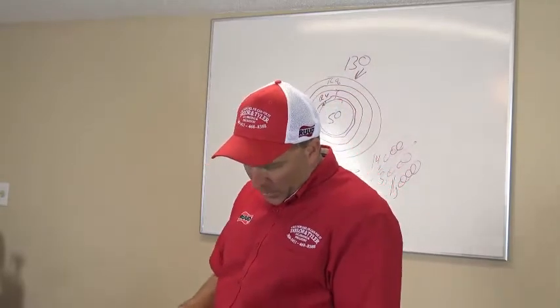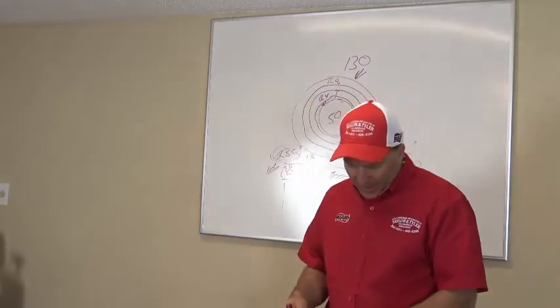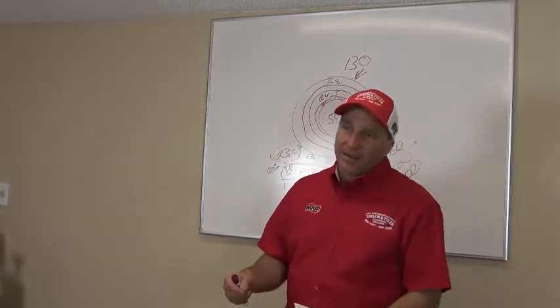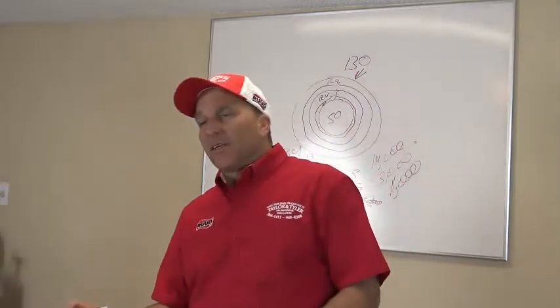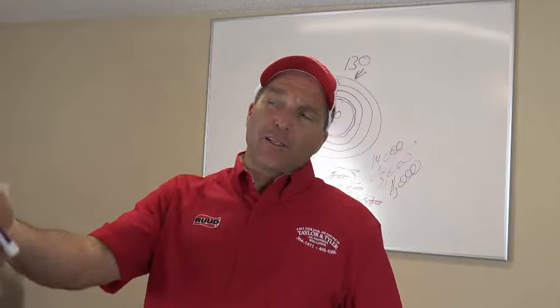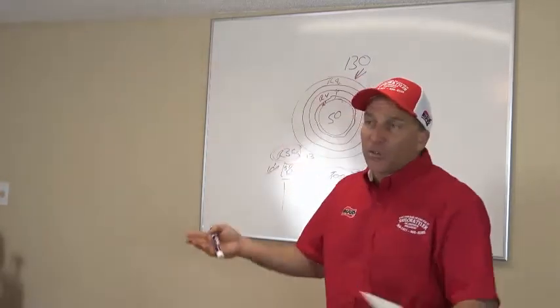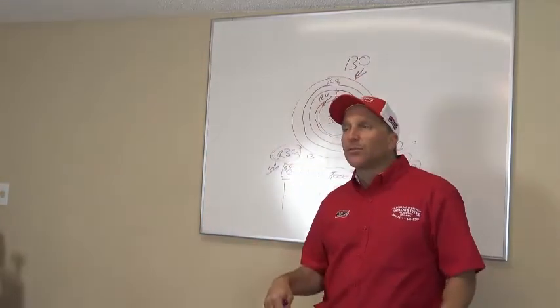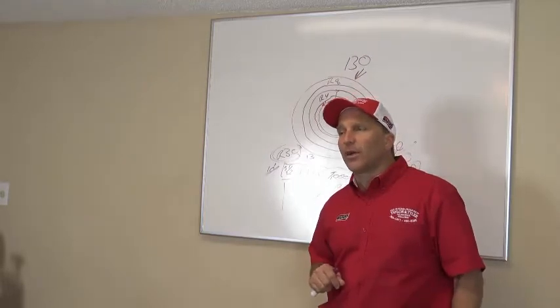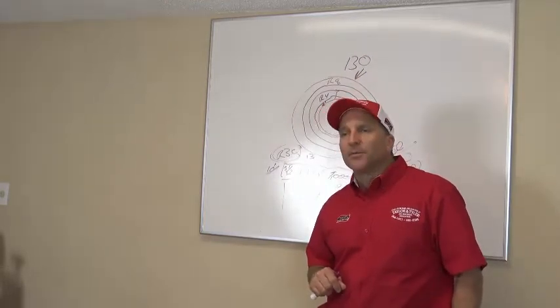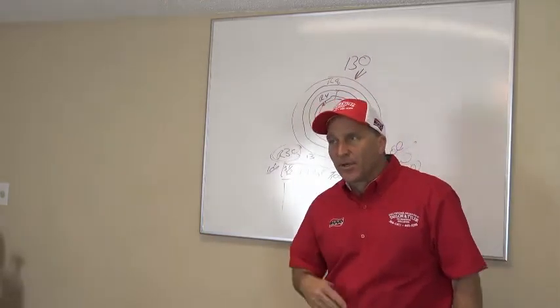Drain lines, okay, uphill or leaking. Drain lines, guys, you've got to look in that attic. And if you've got a 30-year-old system sitting in that attic, or you see that drain line's been there for 30 years, or the house is 40 years old. If the house is 40 years old, how old is the drain line? 40 years? Okay, because it was put in when the house was built.